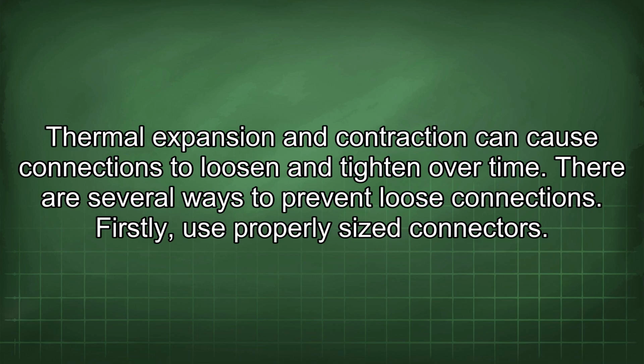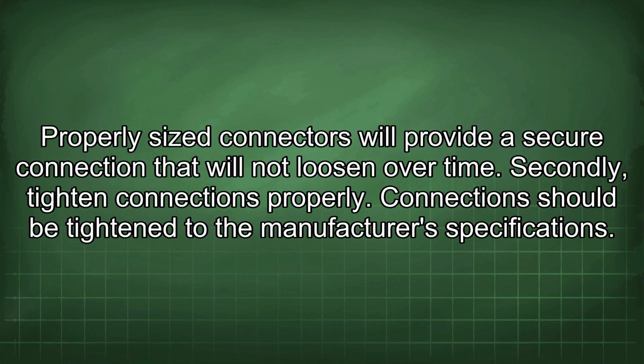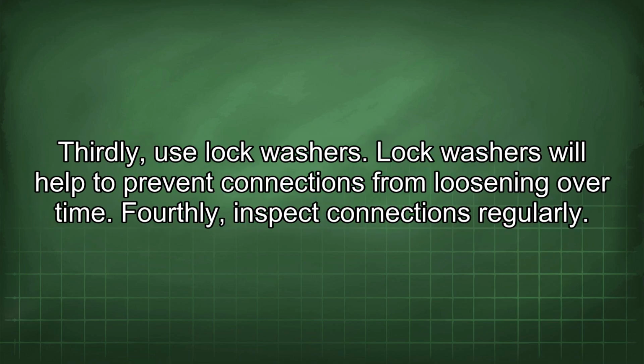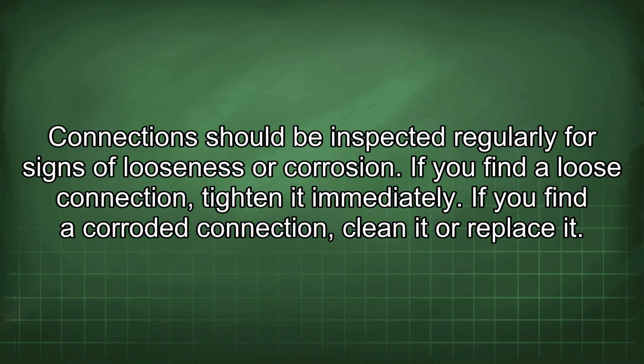There are several ways to prevent loose connections. Firstly, use properly sized connectors. Properly sized connectors will provide a secure connection that will not loosen over time. Secondly, tighten connections properly. Connections should be tightened to the manufacturer's specifications. Thirdly, use lock washers. Lock washers will help to prevent connections from loosening over time. Fourthly, inspect connections regularly. Connections should be inspected regularly for signs of looseness or corrosion. If you find a loose connection, tighten it immediately. If you find a corroded connection, clean it or replace it.